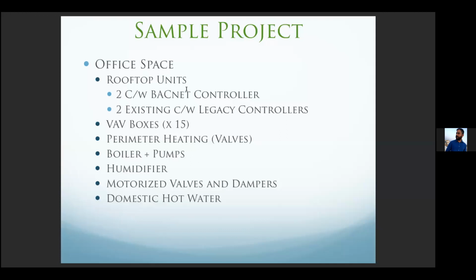So in this scenario, here's what we want to see. If I'm a controls contractor looking at this project, I look at the two BACnet controllers, the two new rooftops that are coming with BACnet controller. So from that perspective, I know that I don't need to account for physically hardwiring a controller to the terminal strip of the rooftop unit. All I need to do is run communication wiring to the rooftop unit, and I'm going to be able to see that rooftop as a device on the front end of the system controller.